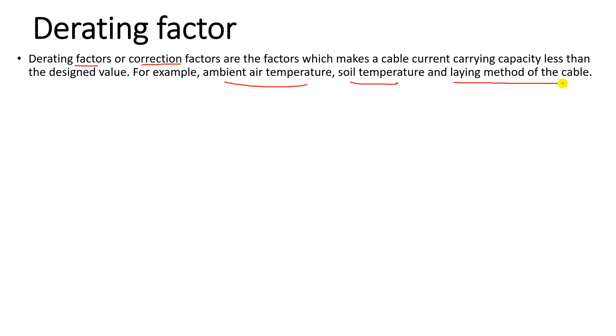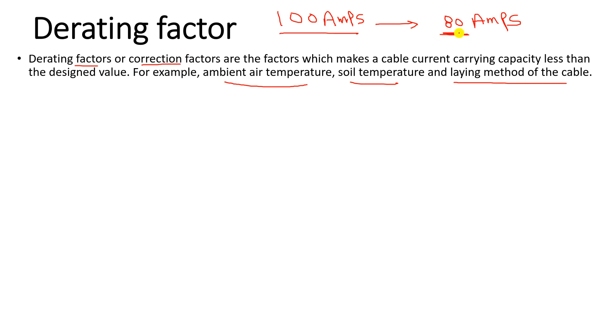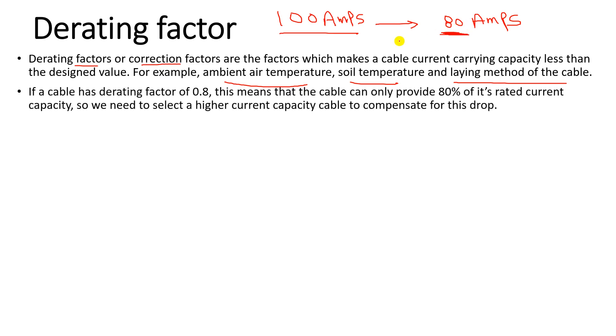Derating means that instead of providing the rated 100 amperes, the cable will only give 80 amperes. Even though it was designed for 100 amperes, conditions such as air temperature lead to a reduced current capacity of only 80 amperes. Derating factors are important — for example, a derating factor of 0.8 means the cable can only provide 80% of its rated current.